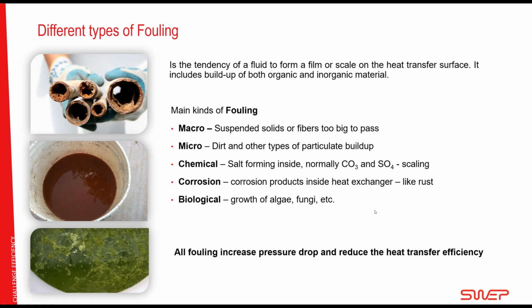So where will we start today? There is a lot of things to say about fouling, and I had to make it simplified. Fouling is macro fouling, suspended solids or fibers that are too big to pass something. Micro fouling, dirt and other things that precipitate, particulate buildup, sorry. Chemical fouling, scaling, corrosion, when corrosion is forming inside the heat exchanger, typically rust. We will not talk about this a lot today since the brazed plate is made of stainless steel, there is no rust buildup. So corrosion is what we're going to speak the least about. And biological is mostly when it's surface water or seawater, and I will put that into macro and micro to simplify things.